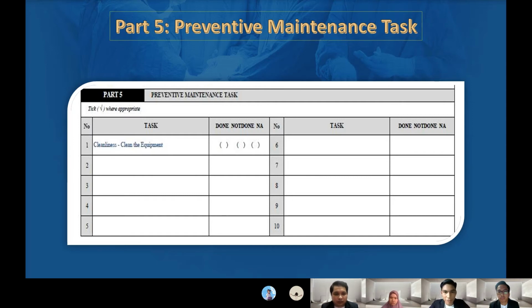What kind of tasks do we have? We need to check the cleanliness of the equipment. In the column we have three options: done, not done, and not available. So what is the cleanliness of the equipment? For example, prior to sterilizing, inspect the patient leads and the fulgurating and coagulating tip for integrity and cleanliness, and for any bit of tissue or carbon that would interfere with proper function, or we need to clean all the electrical contacts.